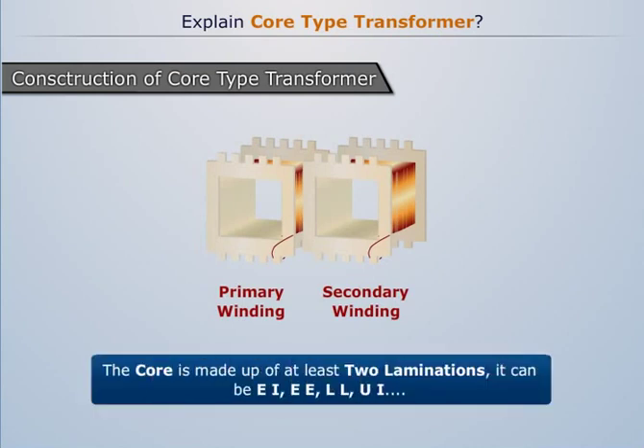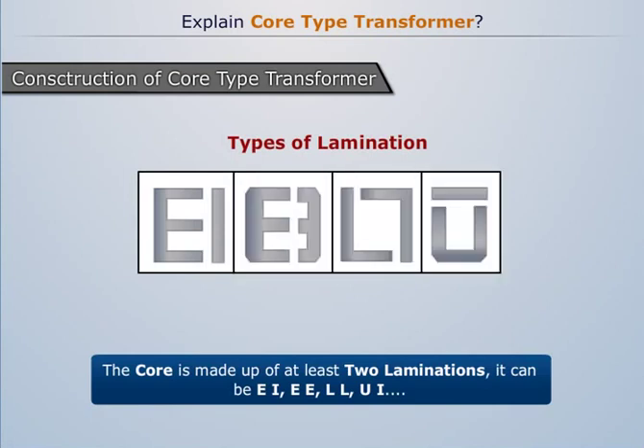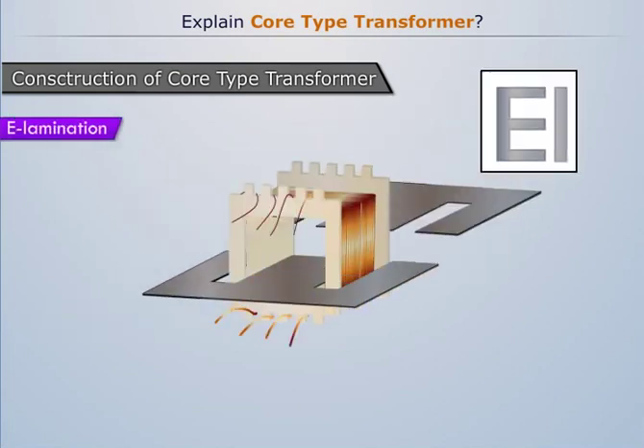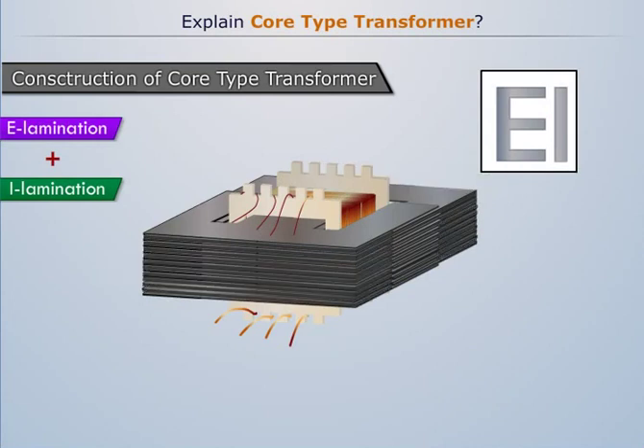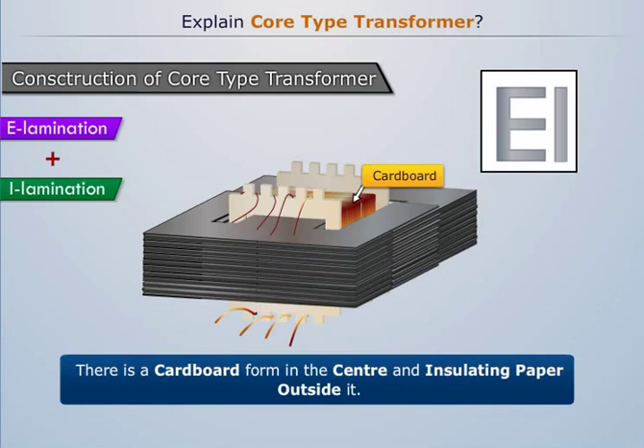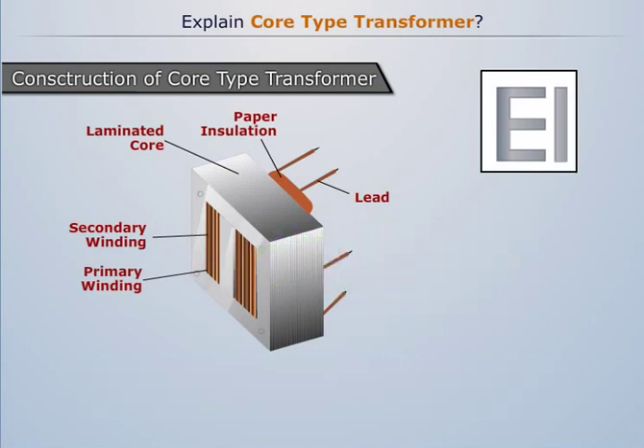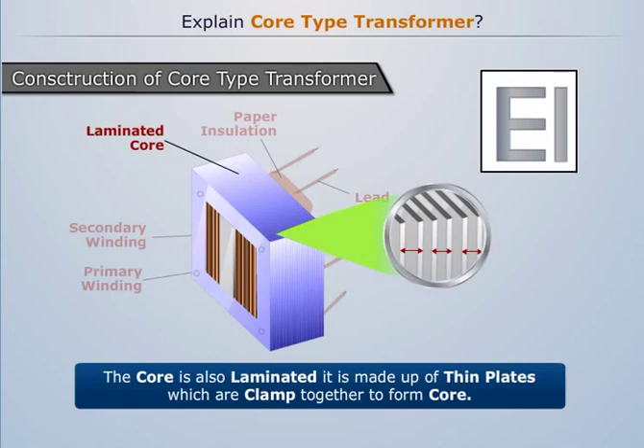The core is made up of at least two laminations; it can be EI, EE, LL, or UI type. In the EI lamination of a core type transformer, there is a cardboard form in the center and insulating paper outside it. The primary windings are placed beside the central core and the secondary windings are just beside the primary. The core is laminated — made up of thin plates which are clamped together to form the core.